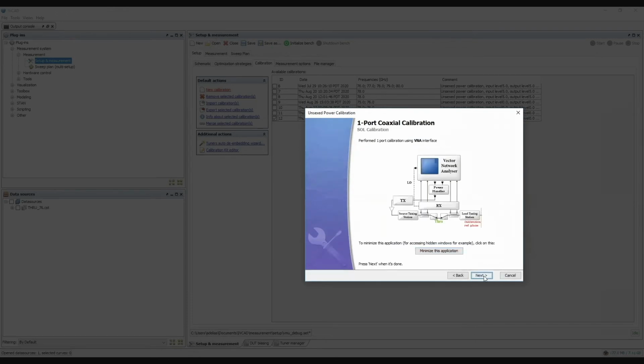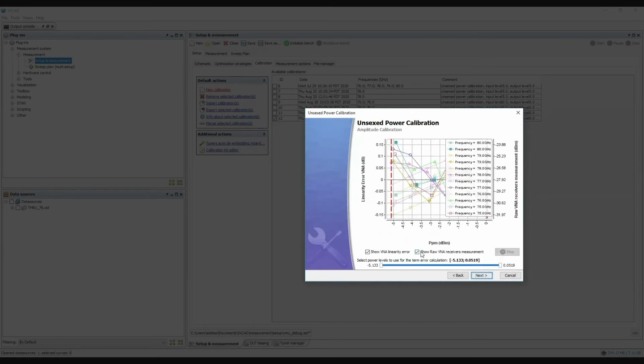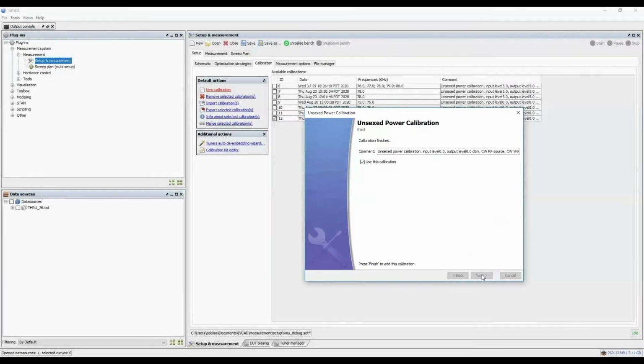The final step in the system calibration is to perform a power calibration. To do this, we first perform a one-port calibration at a desired reference plane and then connect the power meter at the same reference plane. This will ensure the correct propagation of the power calibration coefficient from the one-port reference plane to the two-port reference planes. With this step, we finish the system calibration.